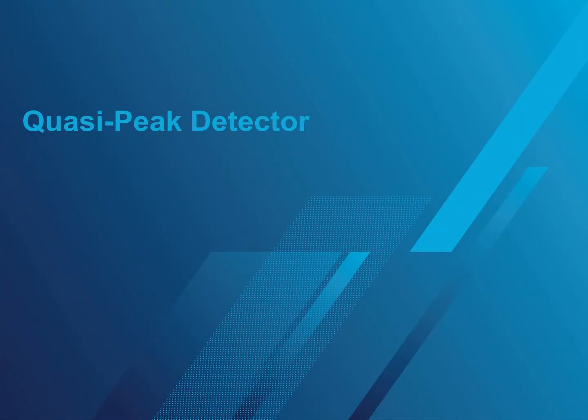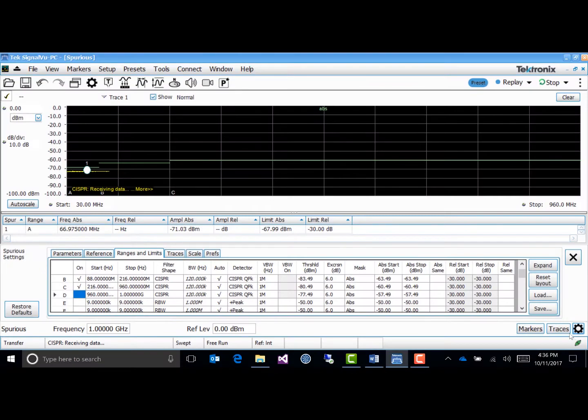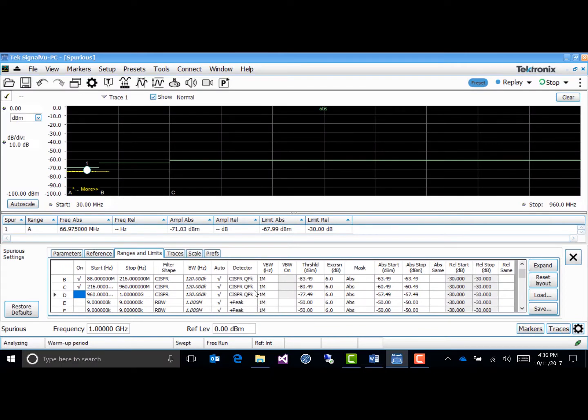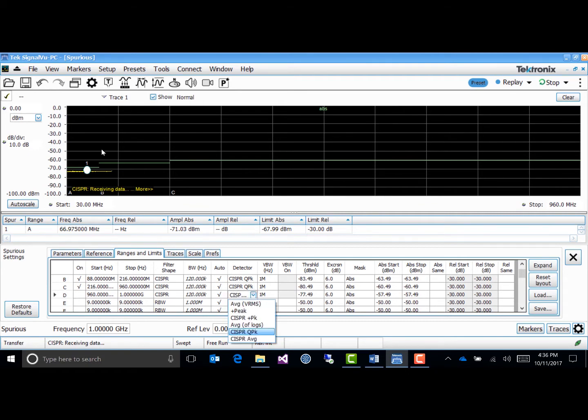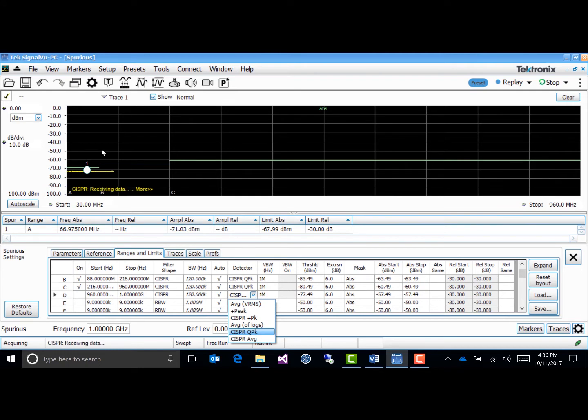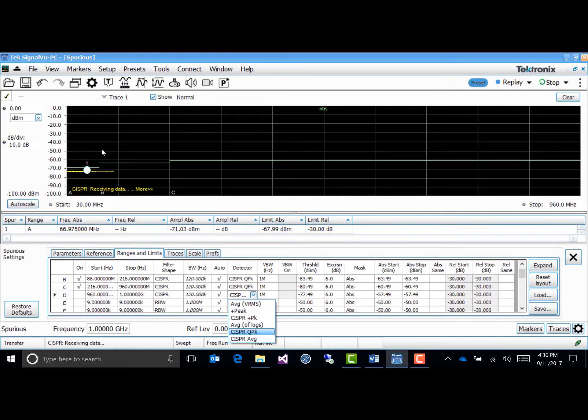Our USB-based instruments are particularly suited as low-cost pre-compliance testers for electromagnetic compatibility, or EMC, testing. To get comparable results to a compliance-level receiver, you must use the correct filters as specified by the EMC standards bodies, the FCC and the CE. These include the CISPR, quasi-peak detection, and averaging methods. These detectors and methods are now available as a low-cost option.